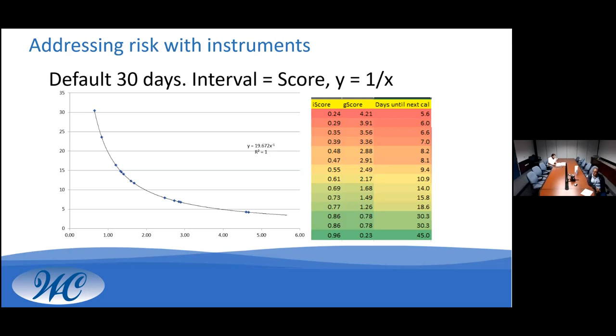By basing our algorithm off of a dynamic y equals inverse x function, the interval between calibration drops significantly faster if any problems are detected. As soon as the pre-calibration data indicates that a sensor is beginning to drift, the interval is tightened to prevent an instrument falling out of calibration before it returns to the lab. With the transition to digital records, we also had more time to record more information, and we decided to also record as found our pre-calibration data.